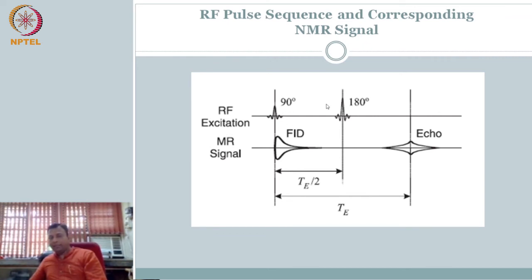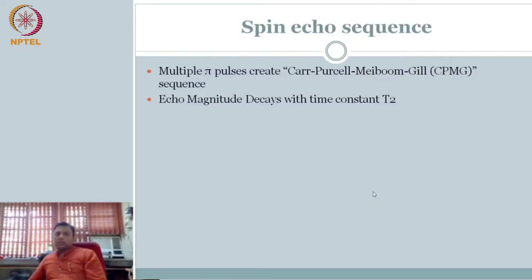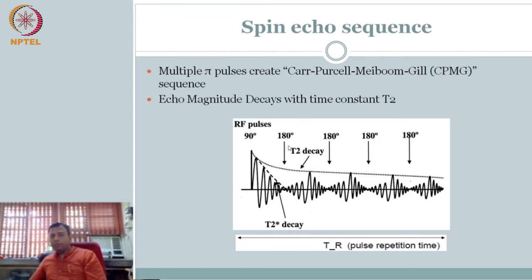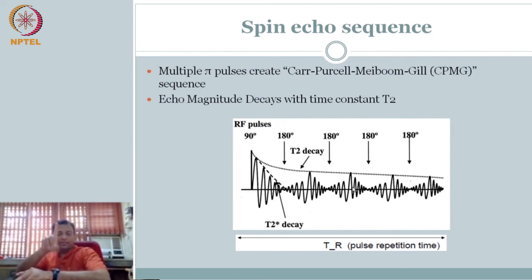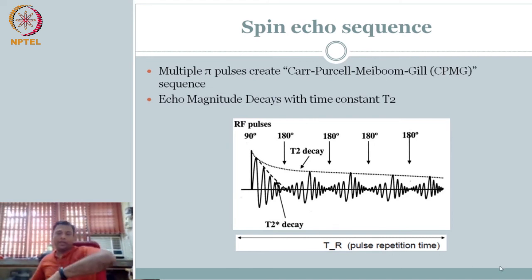So initially you have the RF excitation, then the MR signal — what I am measuring is going to be the echo signal. I have to design the TE and TE by 2. This is called a timing diagram and a pulse sequence diagram, because I know the sequence: 90 degrees and then I am giving 180 degrees after TE by 2, to get a signal that is an echo signal. So multiple pi pulses can be created — essentially you have 90 degrees and then you are applying multiple pi pulses.